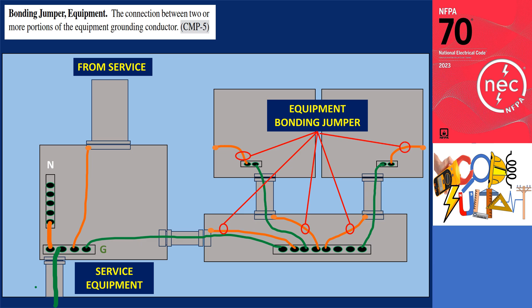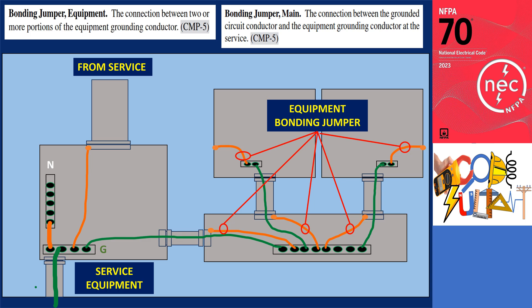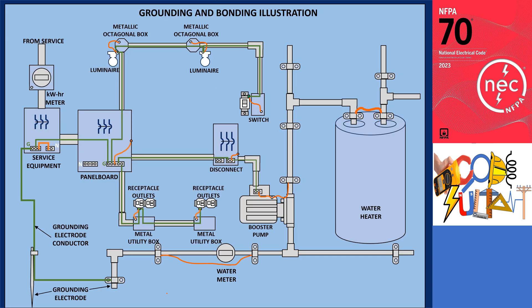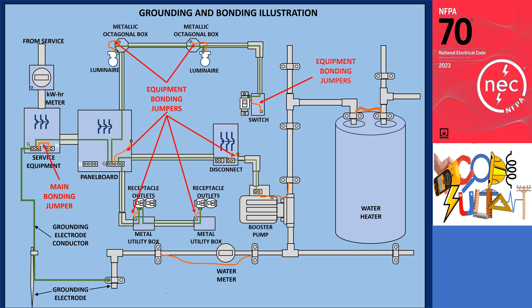The main bonding jumper is the connection between the grounded circuit conductor and the equipment grounding conductor at the service. In one of our illustrations, the bonding jumper that links the equipment ground bus and the neutral bus serves as an example of a main bonding jumper. Sometimes the grounded conductor is linked to the grounding electrode conductor. It's important to differentiate between an equipment bonding jumper and a main bonding jumper. The main bonding jumper is located in the service equipment, while equipment bonding jumpers are installed on the load side of a service, feeder, or branch circuit overcurrent device.